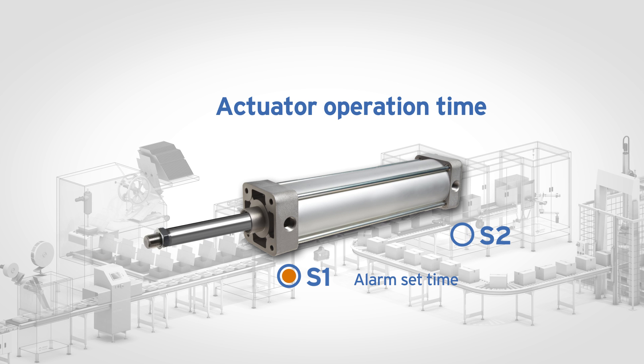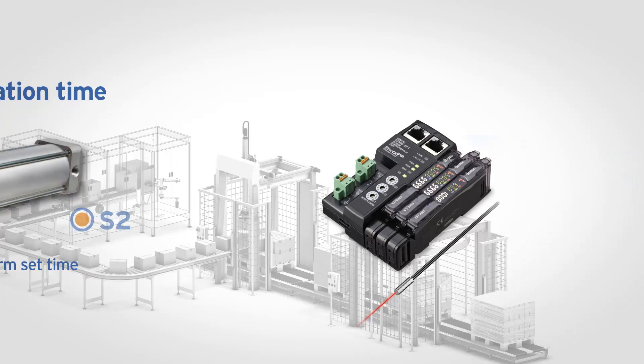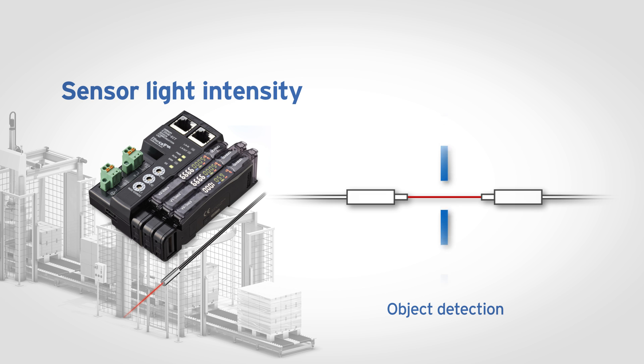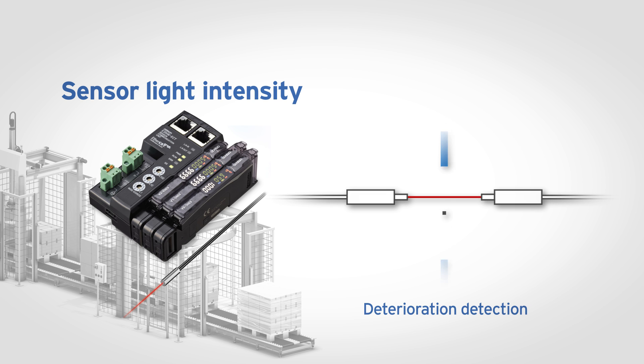The cylinder operation time is measured against a normal operation range, informing if the time exceeds or is lower than this value. The fiber sensor light intensity is monitored for deterioration to detect build-up of dust or other materials.